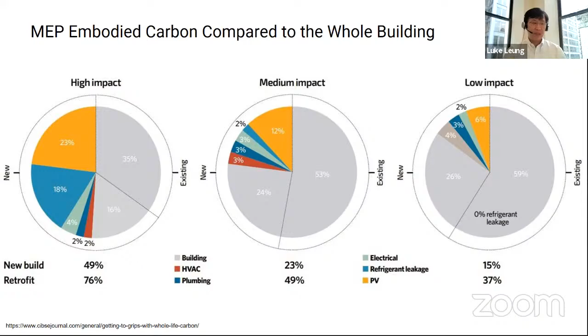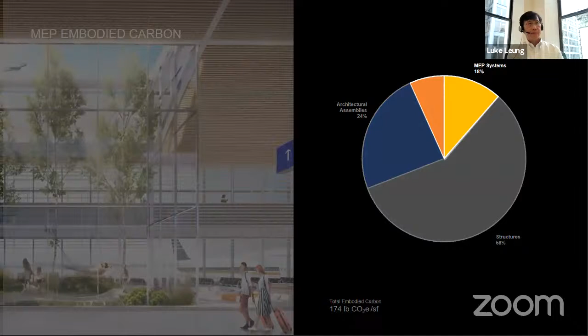This is the O'Hare Airport embodied carbon. We found that refrigerant, the orange piece, makes up 7%—so refrigerant is actually an important part of the embodied carbon discussion. MEP is 18%, and of course there's high-performing equipment. In this case, at O'Hare, we're able to leak less refrigerant and use more efficient, high-performance equipment, which accounts for the percentage difference.